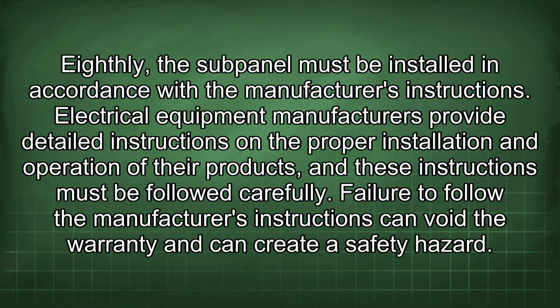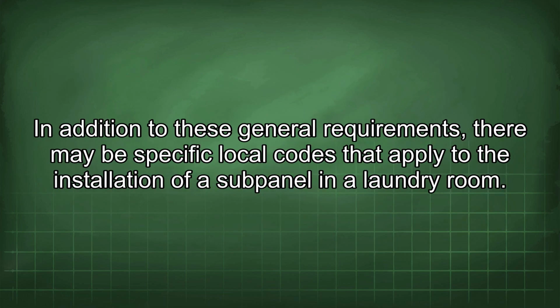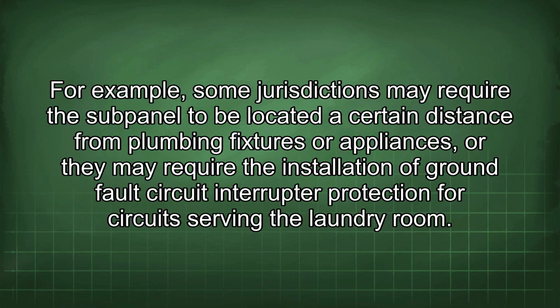Eighthly, the subpanel must be installed in accordance with the manufacturer's instructions. Electrical equipment manufacturers provide detailed instructions on the proper installation and operation of their products, and these instructions must be followed carefully. Failure to follow the manufacturer's instructions can void the warranty and can create a safety hazard. In addition to these general requirements, there may be specific local codes that apply to the installation of a subpanel in a laundry room. For example, some jurisdictions may require the subpanel to be located a certain distance from plumbing fixtures or appliances, or they may require the installation of ground fault circuit interrupter protection for circuits serving the laundry room.